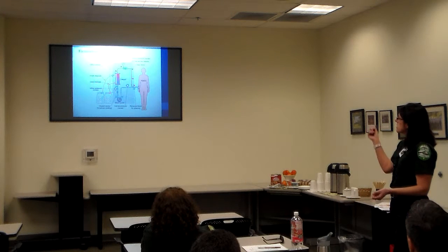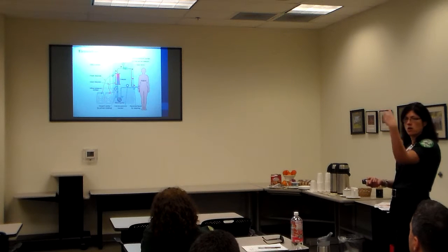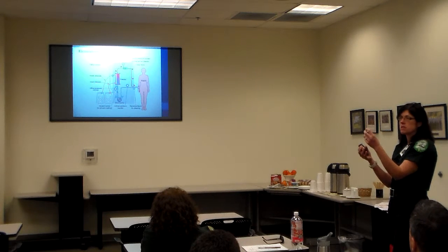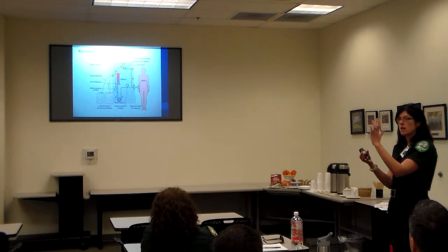And then basically it goes through the dialyzer. The dialyzer has the blood going in one way, and the dialysate flows the opposite direction, and it helps drag all those waste products. And pressure is applied on the membrane to actually decide how much fluid is being removed. Because if you just allowed it to keep going, you could pull off a litre of fluid in 15 minutes if you wanted to.